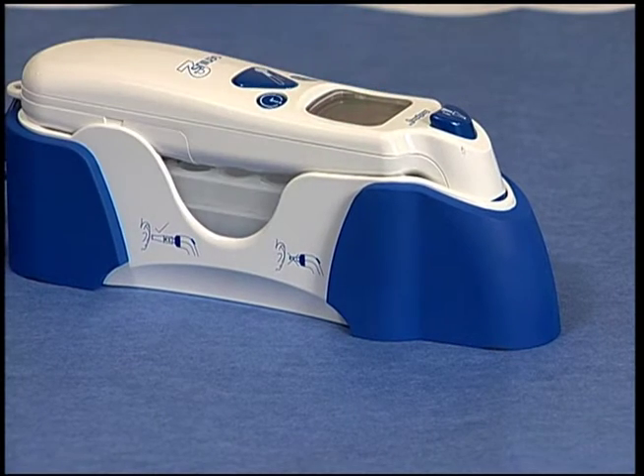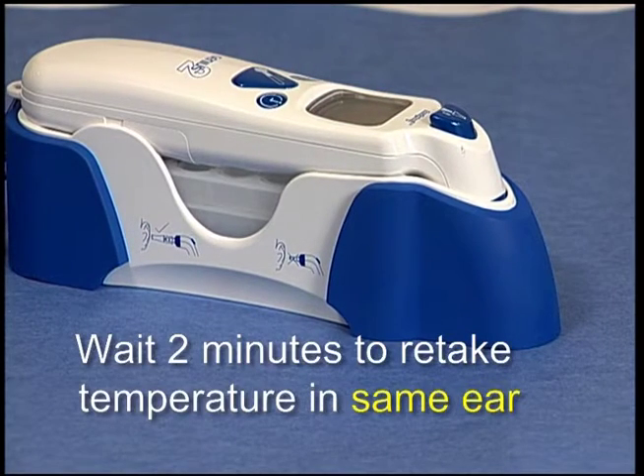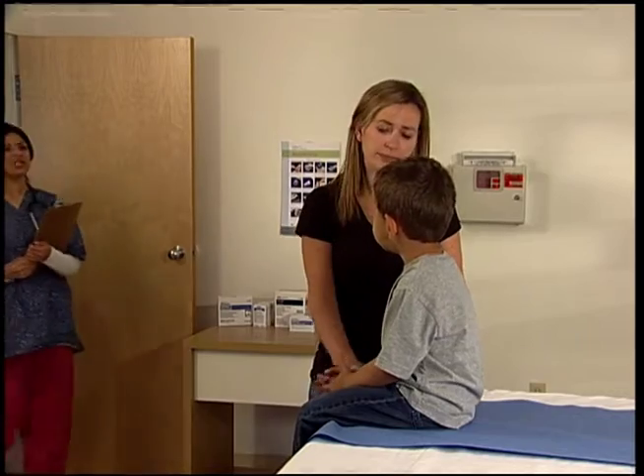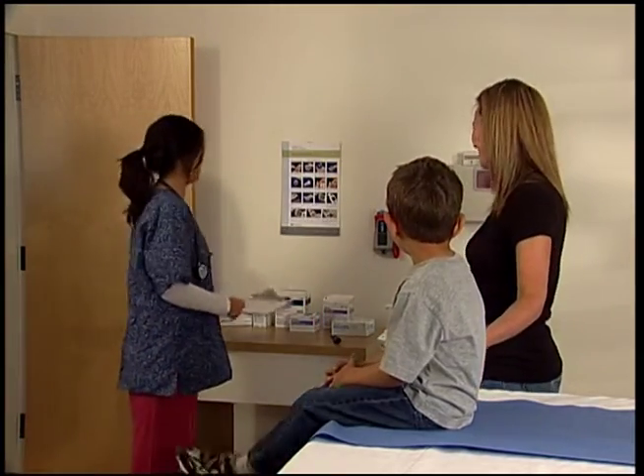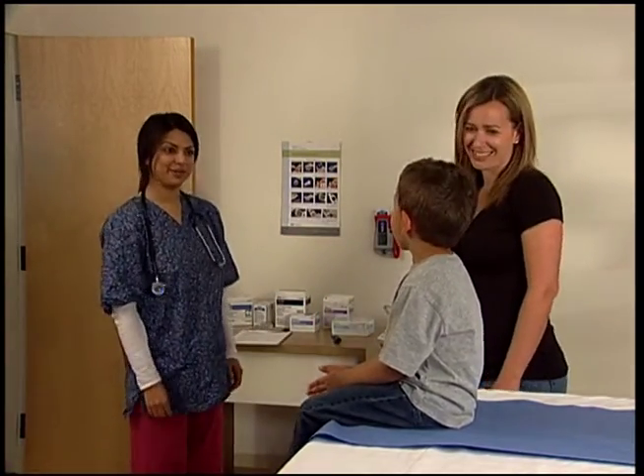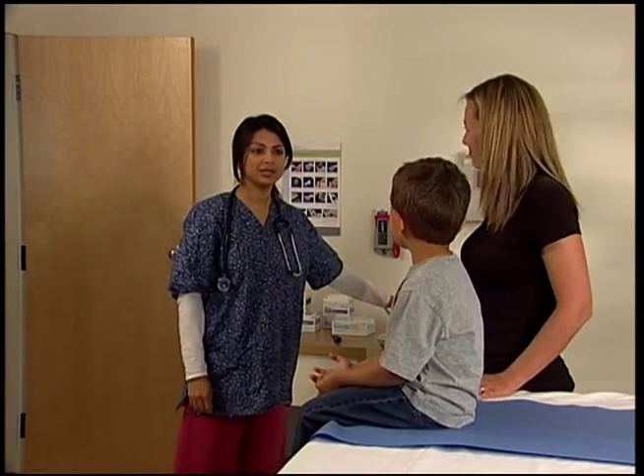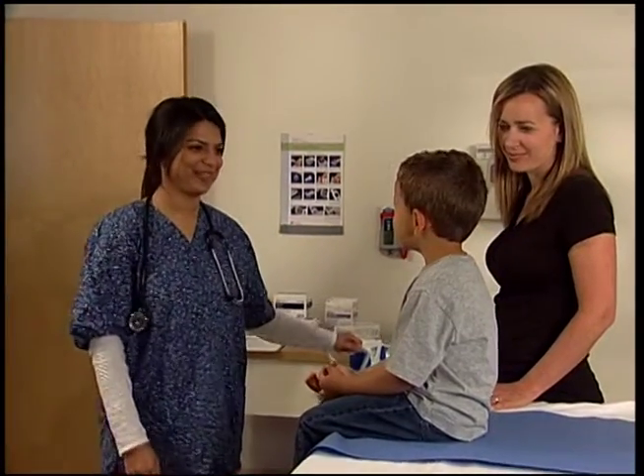If you wish to take another reading in the same ear, you should wait for at least 2 minutes for the ear to return to pre-measurement temperature. For the pediatric population, the tapered probe tip design enables the Genius 2 thermometer to easily fit into and align with the pediatric ear canal.